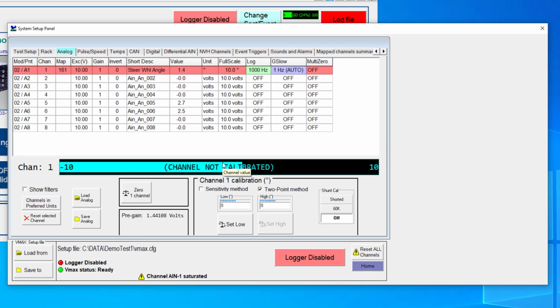So what I'm going to do in this particular case is go ahead and change my excitation voltage to something lower. So we can go as low as 3.3 volts, and we can go as high as 12 volts on our latest modules. The module I have here can only go to 10 volts. But for example, if I set this to something like 9 volts, now, when I move this sensor all the way one direction or the other, I won't actually clip that signal.